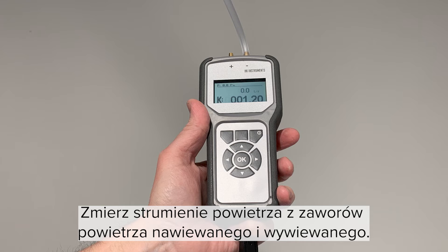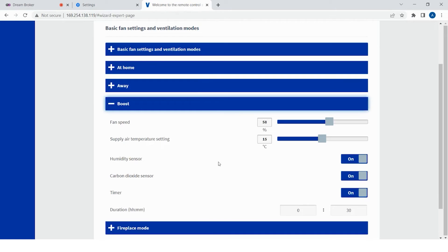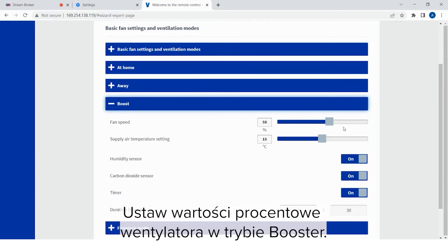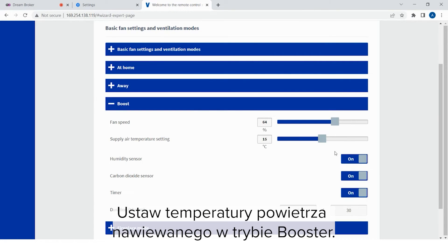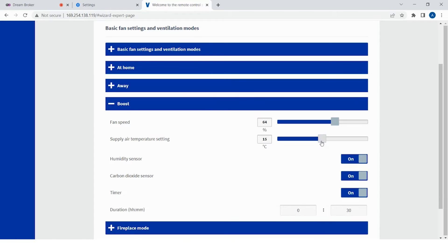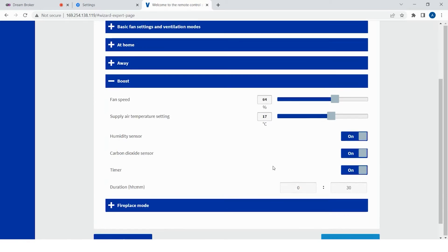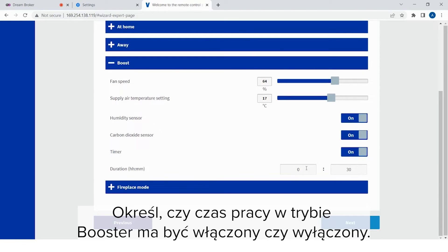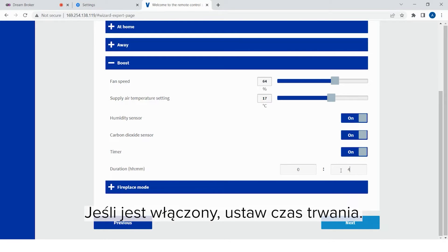Adjust the supply and the extract air flows of the boost mode. Measure the air flows from the supply and extract air valves. Select boost in the menu. Set the fan percentage of the boost mode. The supply and extract air ratio is the same as at the at-home mode. Set the supply air temperature of the boost mode. Ensure that the humidity and the carbon dioxide base controls are turned on. Select whether the timing of the boost mode is turned on or off. If on, set the duration of the boost.